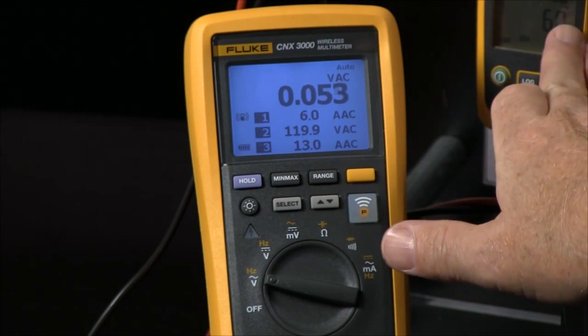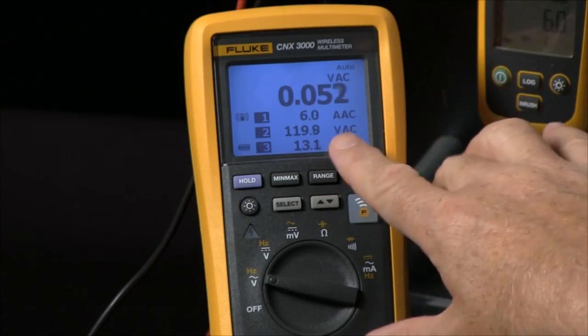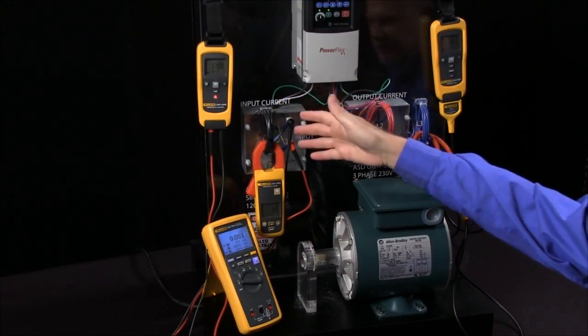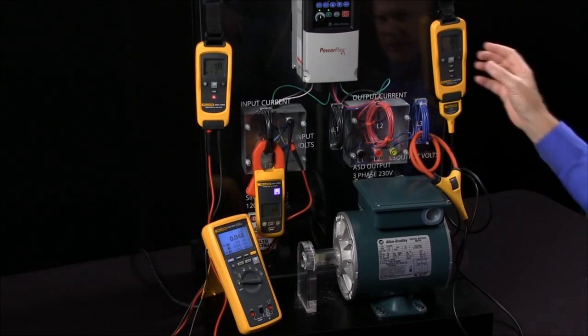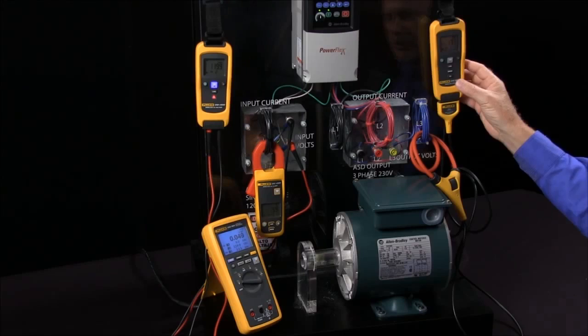Once they're selected, I could either wait or just hold in the arrow button for two seconds and it will turn them on. Here we can see we have six amps coming in to the input of the drive. We have 119.9 volts being measured at the input going into the drive.